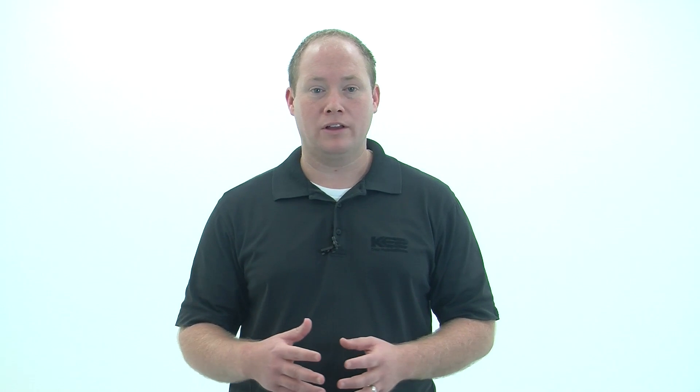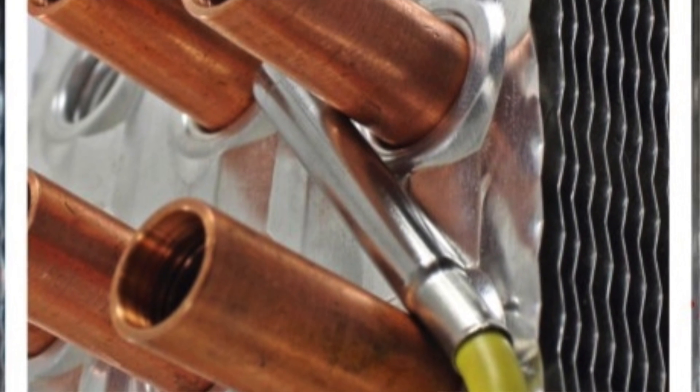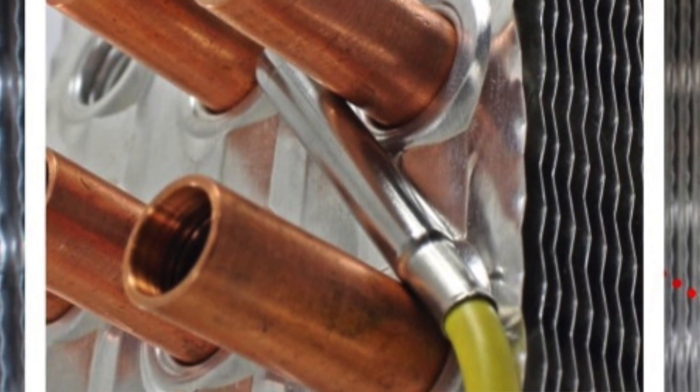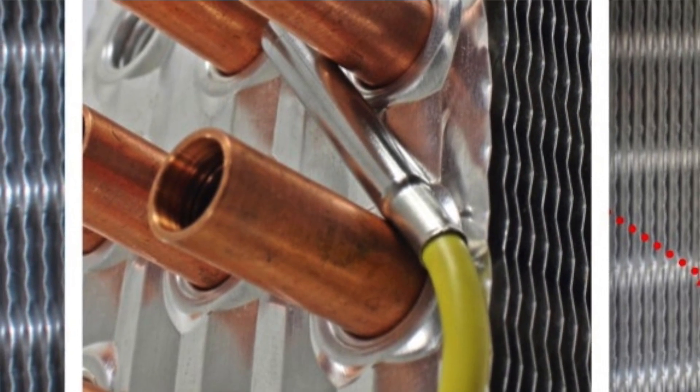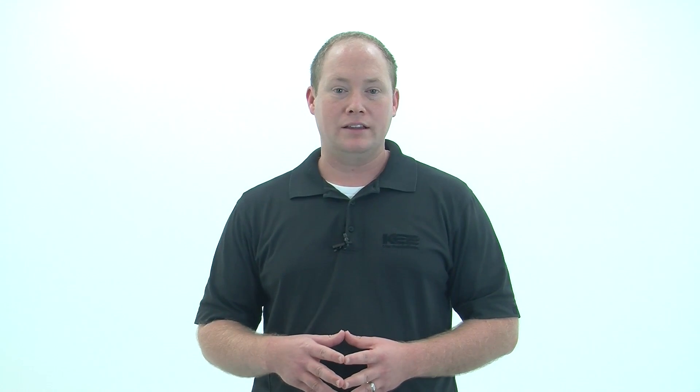The first is to insert the sensor into the coil at a 45 degree angle. When inserting the coil sensor into the coil, it should be angled upward with the cable hanging downward. This allows moisture to drain away from the sensor.